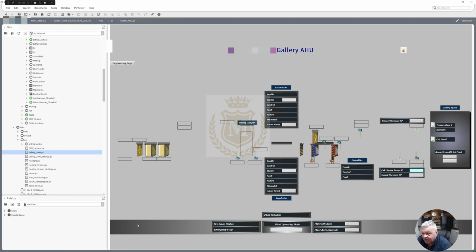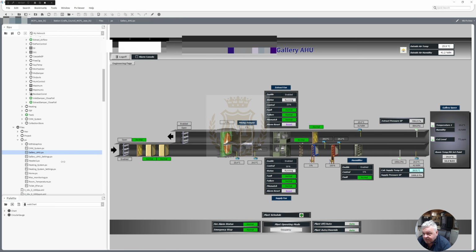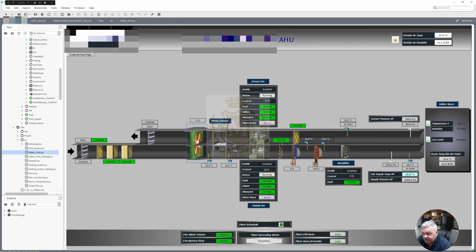If I go to my PX here and go to my gallery AHU, this is another air handling unit, and we've got a thermal wheel here, as you can see. We are extracting 23.3 degrees temperature through that panel filter, through the fan motor. We're not recirculating anything at all. That's at 0, so that is now closed. Even though it's spinning, it's at 0, so we're not recirculating that. So that air is being taken straight to the outside. So 23.3 degrees air is going straight to the outside.